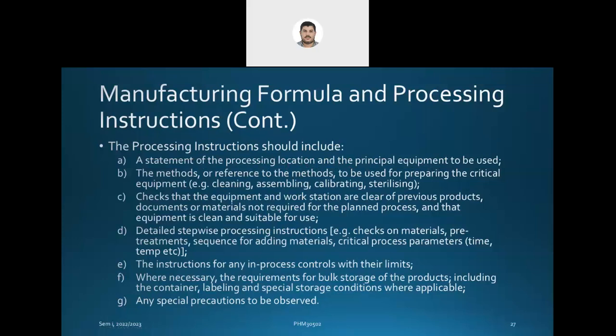Reference to the method means that use the method specified in SOP number, for example, 20,805. Okay, so you get this SOP number 20,805, and then you get the steps for performing this procedure. Okay, used for preparing critical equipment, cleaning the equipment, assembling the equipment, calibrating or sterilizing the equipments we use. Checks that the equipment and workstation are clear of previous products, documents, or materials not required for the planned process, as we mentioned before about packaging.